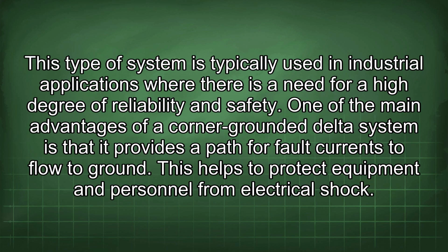This type of system is typically used in industrial applications where there is a need for a high degree of reliability and safety. One of the main advantages of a corner-grounded delta system is that it provides a path for fault currents to flow to ground. This helps to protect equipment and personnel from electrical shock.